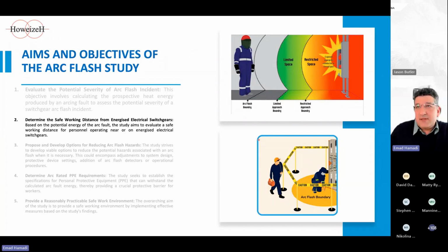So, the safe distance is crucial, and I've seen in many sites they mark the floor with the arc flash boundary, which is a very good practice. For example, in one of the projects where we were designing the electrical network, the client asked us to conduct the arc flash study in the early stage of the project. Based on the arc flash boundary and the safe working distance, they designed the equipment layout and the civil work of the enclosure, marking up the floor and walking path, which was a very good practice, I would say.